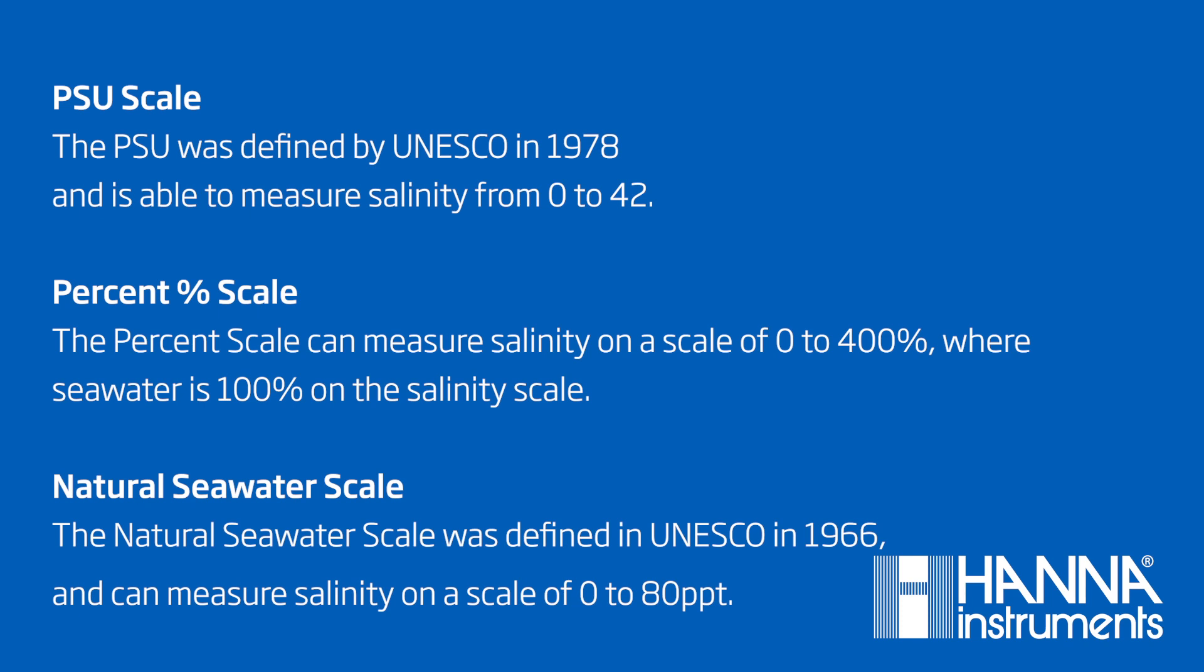The PSU was defined by UNESCO in 1978 and is able to measure salinity from 0 to 42. This scale is a conductivity ratio and does not have any units. The percent scale can measure salinity on a scale of 0 to 400 percent. The natural seawater scale was defined by UNESCO in 1966 and can measure salinity on a scale of 0 to 80 parts per thousand. These measurements, when using an EC meter, are considered indirect because the final number displayed is calculated via an algorithm within the meter.